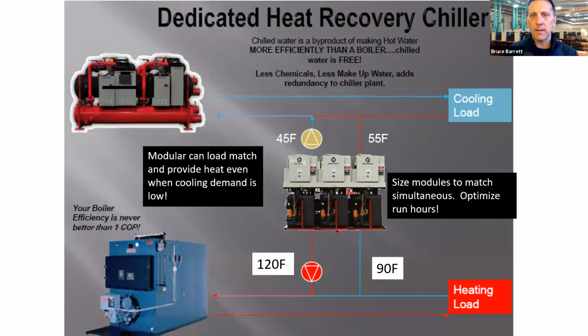Again, just a quick summary. Matching your simultaneous load is very easy with a modular chiller. It's a simple configuration, 2 pumps, 4 pipes, and a very, very small footprint. You can get the quality of temperature that you need across different loads without sacrificing your kW per ton making hot water.